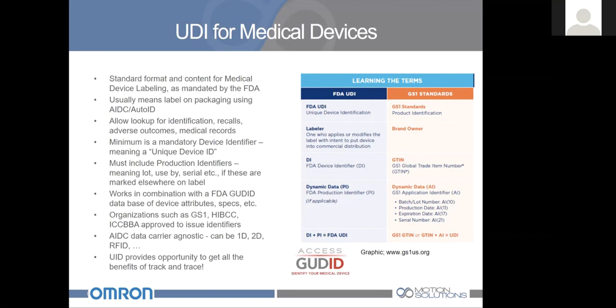While the UDI rule does not require the use of specific forms of AIDC, auto ID, or specific technologies to present the UDI, the AIDC form of the UDI should be in a format that can be read by a barcode scanner or some other type of AIDC technology. The labeler may choose to use more than one type of AIDC technology form to assist users who may be employing different methods of UDI capture technology. As an example, we could have on that label both a linear barcode and a 2D data matrix code. Some readers would only be able to read a linear barcode, such as a laser barcode scanner.